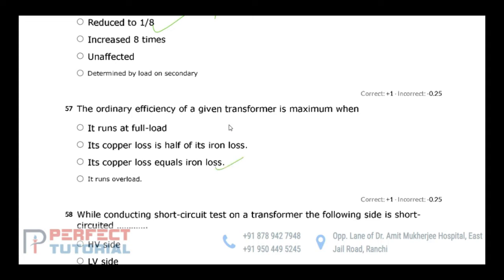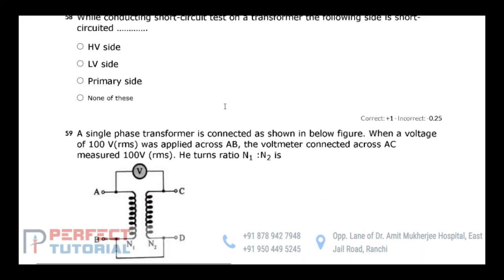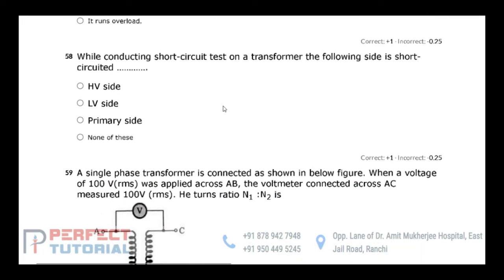Next, while conducting short circuit test on a transformer, the following side is short circuited. See, short circuit test is preferable to conduct on HV side, keeping LV side short circuited, because of the several advantages. As a very low voltage is sufficient to conduct this test, as a HV side it can be conducted. And see, if you conduct the short circuit test on HV side, the measuring instruments available in the laboratory can be used to measure conveniently the parameters under short circuit test. So on HV side, the testing equipments are to be connected and on LV side, it is kept short circuited.